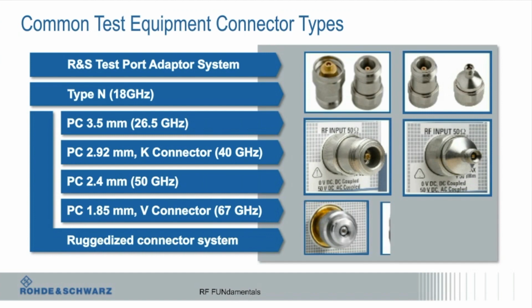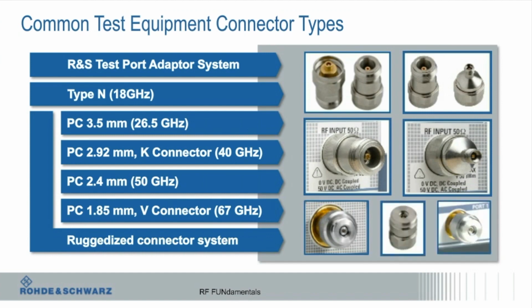These are all ruggedized so that you can make lots and lots of insertions. That's really the intent of metrology grade connectors: you're going to make lots of insertions, and it's very, very repeatable over lots and lots of insertions.